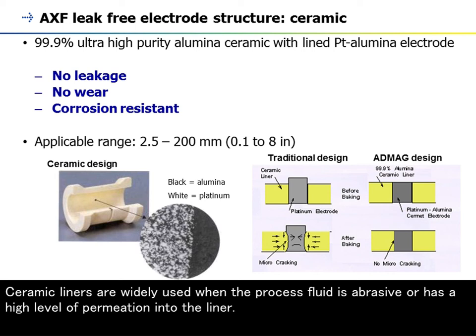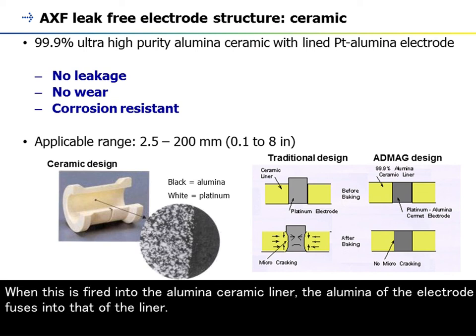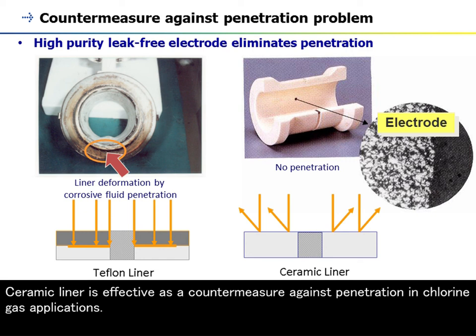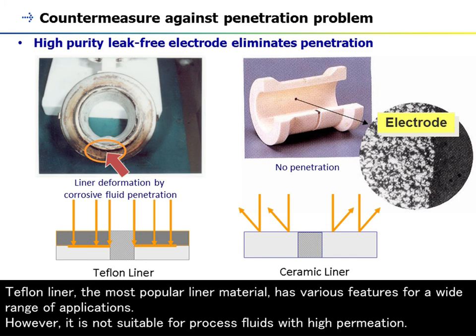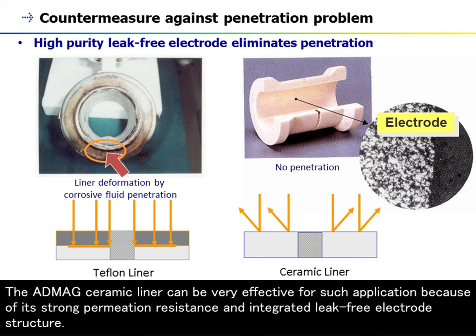Ceramic liners are widely used when the processed fluid is abrasive or has a high level of permeation into the liner. For the ceramic-lined ADMAG AXF, the electrode is a powdered cermet of alumina and platinum. When this is fired into the alumina ceramic liner, the alumina of the electrode fuses into that of the liner. The liner is 99.9% ultra-high purity alumina ceramic with a fused platinum-alumina electrode. The ceramic liner is standard for sizes 2.5 to 200 mm. Ceramic liner is effective as a countermeasure against penetration in chlorine gas applications. Teflon liner, the most popular liner material, has various features for a wide range of applications; however, it is not suitable for processed fluids with high permeation. For example, brackish water that includes chlorine gas penetrates into the liner and deforms it. The ADMAG ceramic liner can be very effective for such applications because of its strong permeation resistance and integrated leak-free electrode structure.